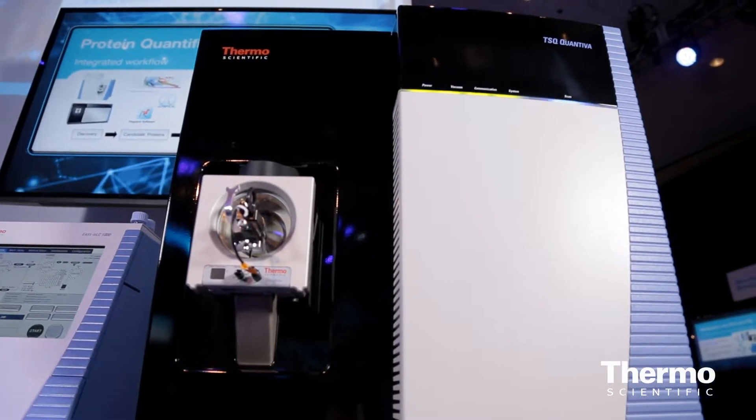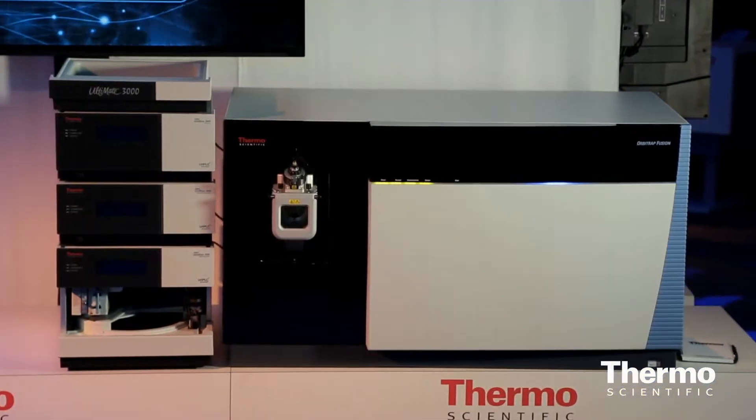We're always pushing the resolution higher and higher with every generation of Orbitrap, of course, but we also push the scan speed faster with dynamic scan management. The Orbitrap Fusion has the unique ability to do both HCD fragmentation — which I refer to as the hammer, because it really hits a molecule hard and gives you a large number of fragments — and CID fragmentation, which we see in the ion traps and is more like a scalpel, where you take a portion of a molecule and can very finely separate it into smaller and smaller portions.